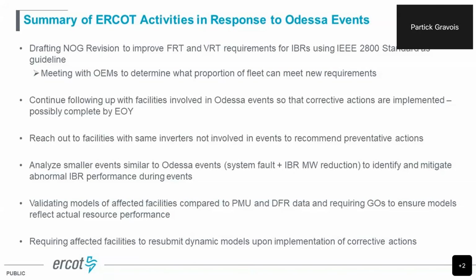We're also analyzing smaller events similar to Odessa, which include both a system fault and a loss in IBR output, to identify and mitigate this abnormal performance during these events. So we have new tools that we're looking at using, real-time PMU data, looking at our ACE to see, hey, there was a loss of solar of more than 100 megawatts. We see a fault occur at the same time. Let's send out an RFI, or reach out to this facility to see why they tripped, to see if that fault was close by to their facilities, and to see if they're really performing the way they should be.